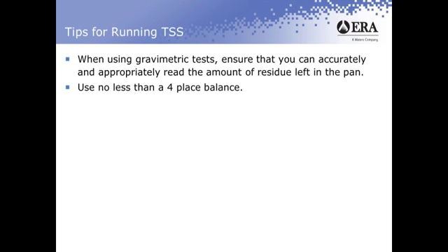number. So let's say we're measuring something and that last place on the balance is a 4. You'll see it go from 4 to 5 to 4 to 5 to 4, maybe down to 3, and a lot of times it doesn't always stabilize in there. And that's called a balance uncertainty.